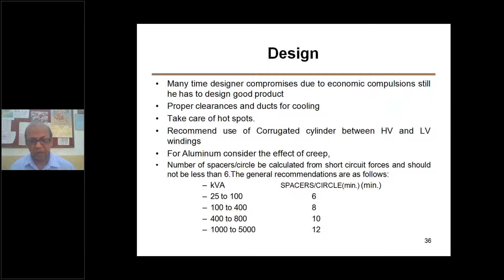Anything else? For aluminum, consider the effect of creep, and how aluminum will behave under creep. The number of spacers per circle is to be calculated from the short circuit forces. So you must do the short circuit calculations and then determine the number of spacers to be used per circle. I'm giving certain thumb rules, which no doubt are to be verified again with the short circuit forces depending on the particular transformer.